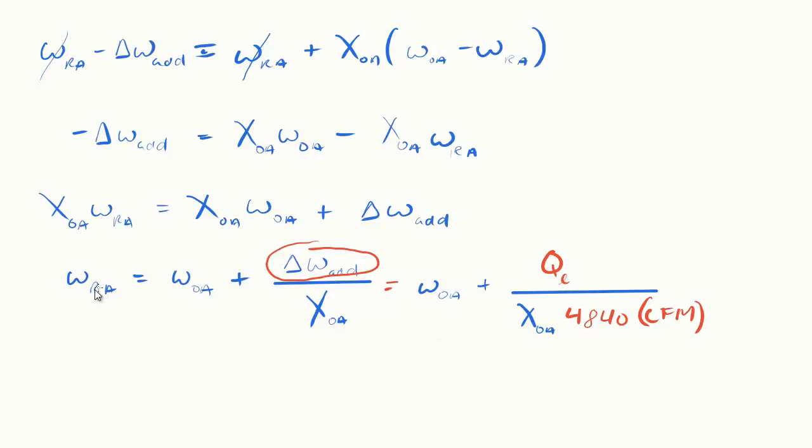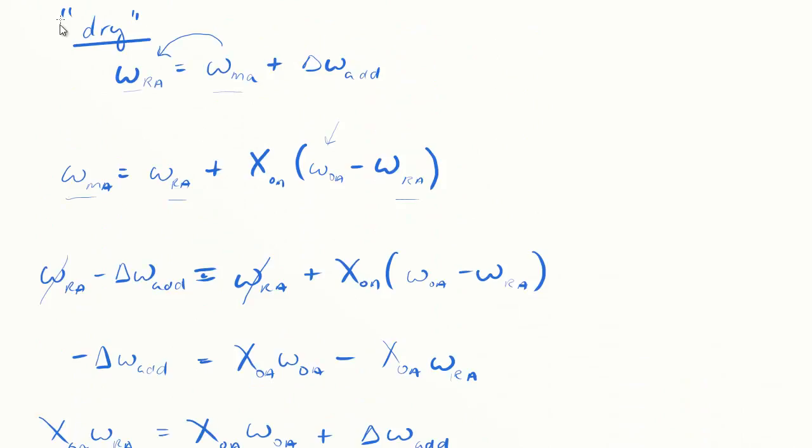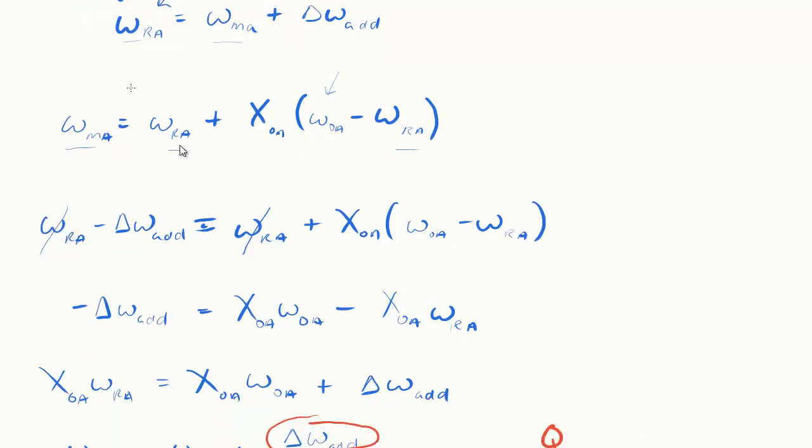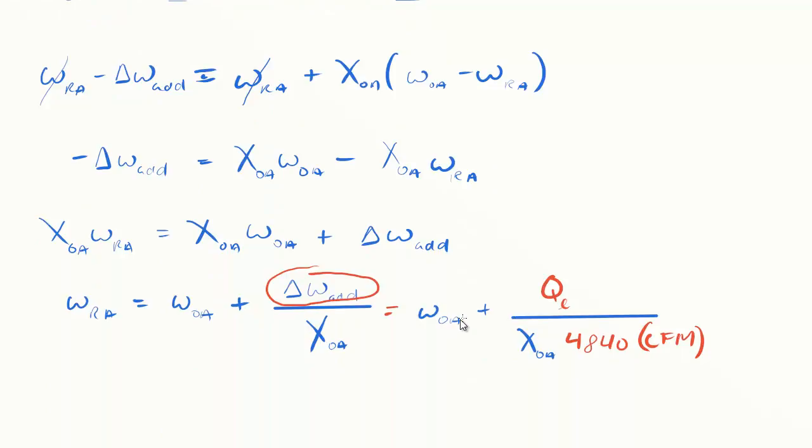If I take this term and put in what we had to start, that omega added was Q latent over 4840 times CFM. I would get omega_OA plus that Q latent divided by 4840 times CFM divided by X_OA. It's an interesting formula - our return air absolute humidity ratio in the dry condition simply adds this term to outdoor air humidity ratio. At no point do you see mixed air or supply air in here.